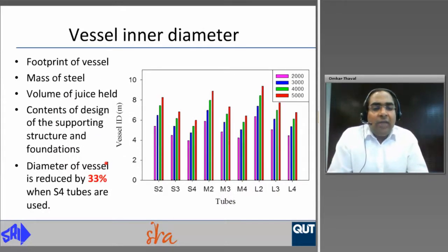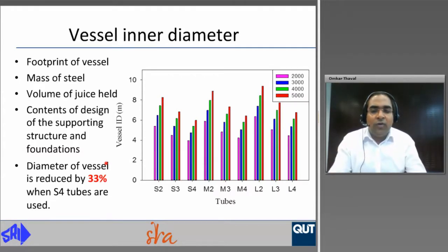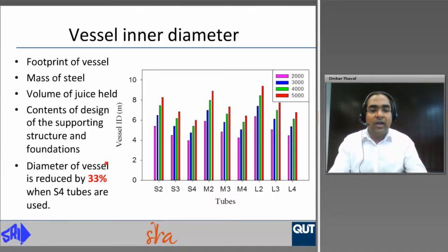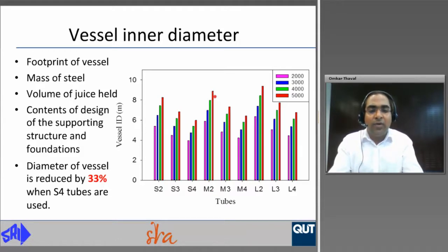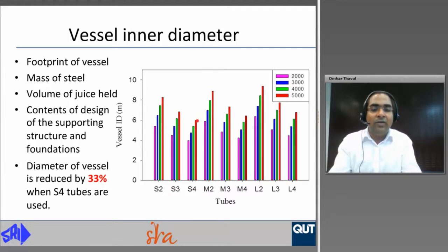The vessel inner diameter is an important parameter as it determines the footprint of the vessel, the mass of steel, the volume of juice held in the vessel, and the requirements for supporting structure and foundations. The diameter is reduced by 33 percent when small diameter 4 meter length tubes are used compared to medium diameter 2 meter length. For example, for 5,000 square meter heating surface area, the vessel inner diameter is 9 meters for M2 tube dimensions and is reduced to around 6 meters when small diameter 4 meter tubes are used.